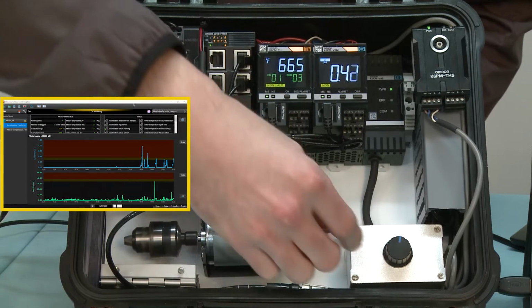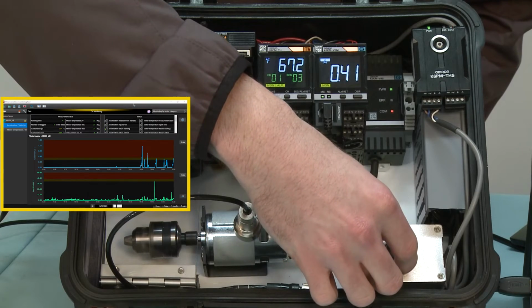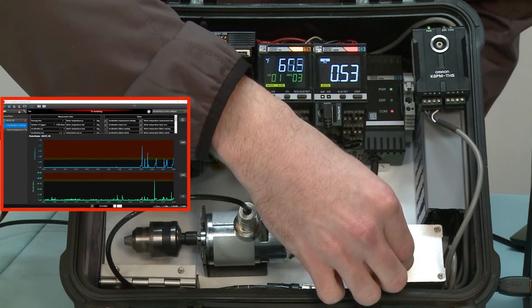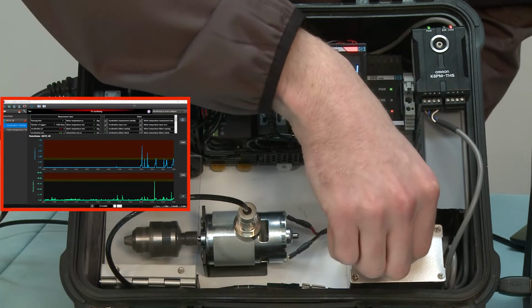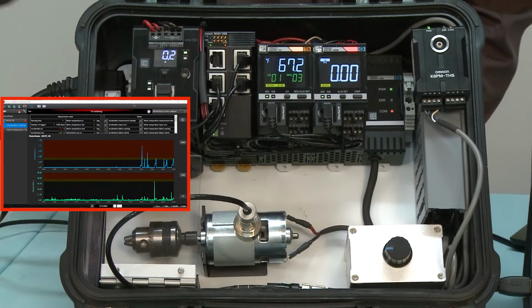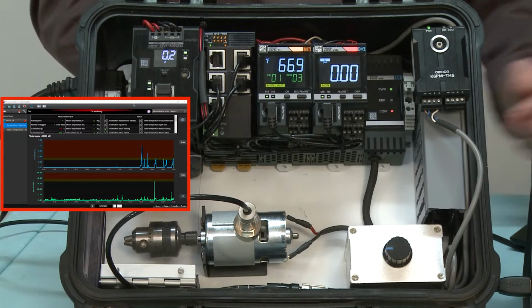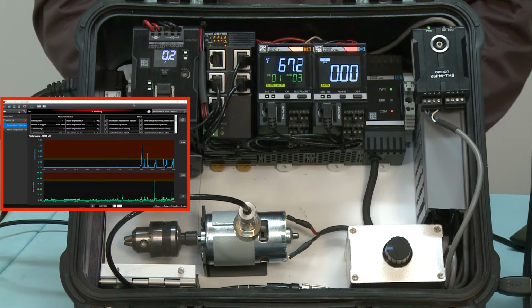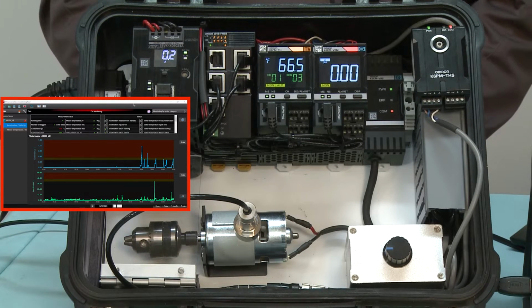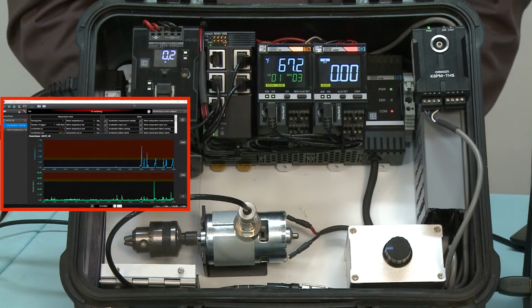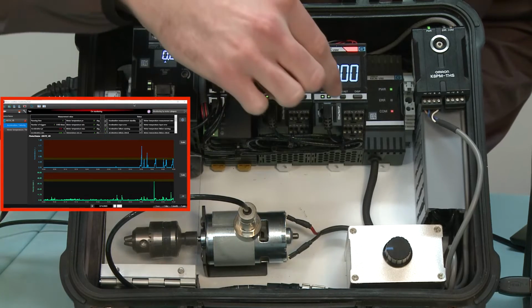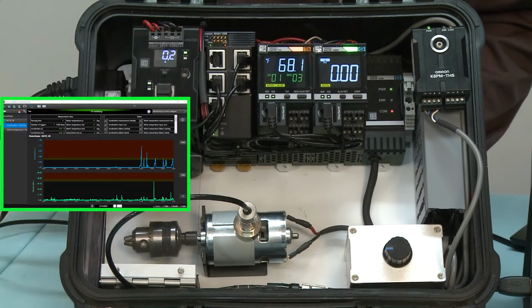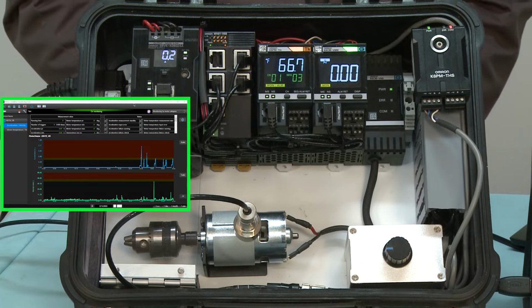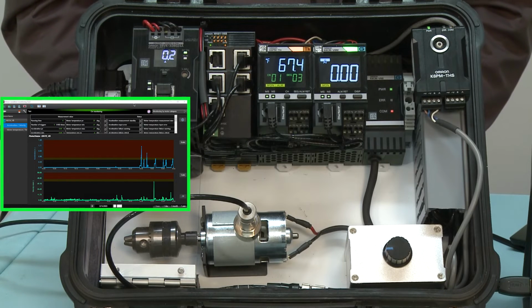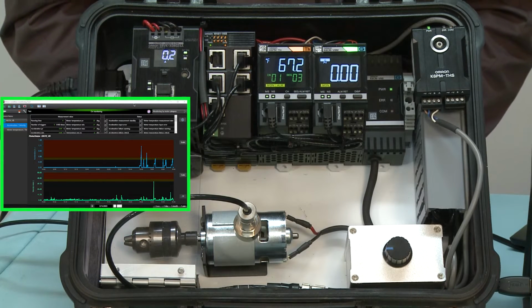Now let's say something's gone catastrophic. I've set that for 0.5 G's. So now something's gone wrong. You can see in my real-time software that there's an issue. There's a critical alarm that's been tripped, and the only thing that can be done to turn that off is maintenance personnel going in and pressing the alarm reset button. Now you'd know right away when something's gone awry, and we can fix an issue before it causes unplanned downtime.